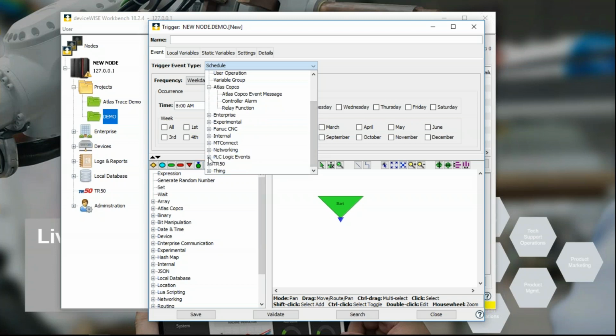Just to not elaborate too much here, we also support what we call PLC logic events. PLC logic events is when the PLC is the master. The PLC knows best when you need to know the data, so when that condition is met, the PLC does a network transmission and sends you the information.